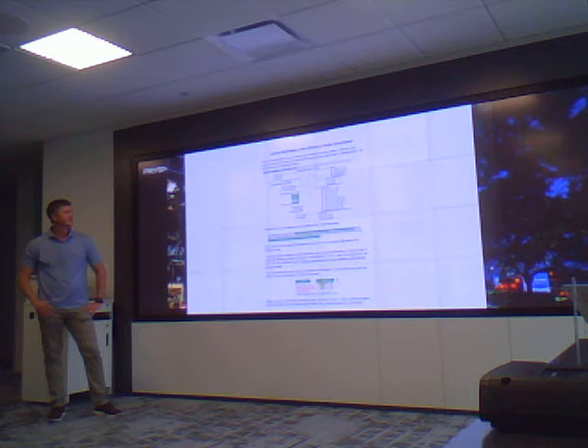So every Lennox unit 036 or above can be a single compressor, dual speed, which makes it multi-stage. Before those came out, it was one compressor, single stage. Except these are multi-stage compressors, two-speed. So even though there's one compressor, it's still a multi-stage unit, and that shows it there.